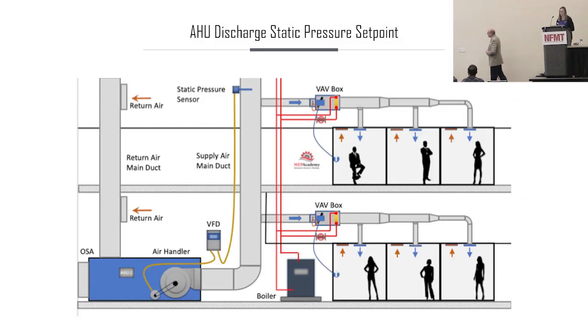Okay, on this next one here, fairly simple. We talked about this early on when I was showing the piping diagram again. Same thing on the air side. That pressure sensor, if they've parked it here inside the mechanical room, the envelope of control on that VSD is not going to be as wide as if we can get that at the distant end and control to that static pressure set point. We can again generally allow the VSD or VFD to follow its programming over a wider range of operating points and get that fan speed down for longer periods of time.